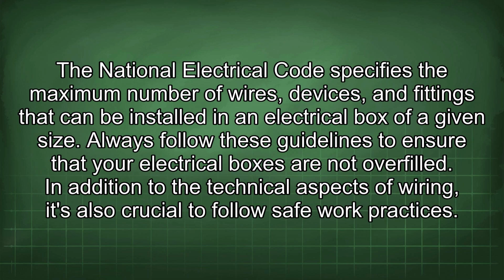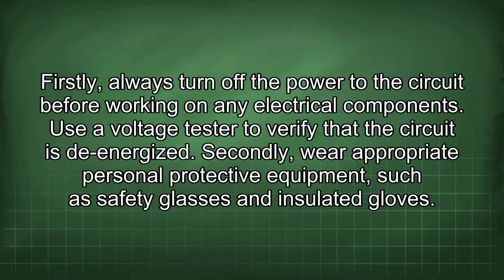The National Electrical Code specifies the maximum number of wires, devices, and fittings that can be installed in an electrical box of a given size. Always follow these guidelines to ensure that your electrical boxes are not overfilled. In addition to the technical aspects of wiring, it's also crucial to follow safe work practices. Firstly, always turn off the power to the circuit before working on any electrical components. Use a voltage tester to verify that the circuit is de-energized.